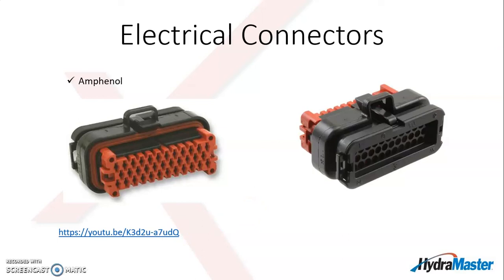One of the other things I might mention while I have this image up here: care needs to be taken if you're testing with this plug. It's really not recommended that you probe these points. This is the end of the connector, the terminal. If you probe them with a lead from an amp meter or a multimeter, it's really easy to damage them. It will expand the pin so that it doesn't make a connection or makes an intermittent connection. So it's really not recommended that you probe them. We do have the mating part to this, and that actually works very well.